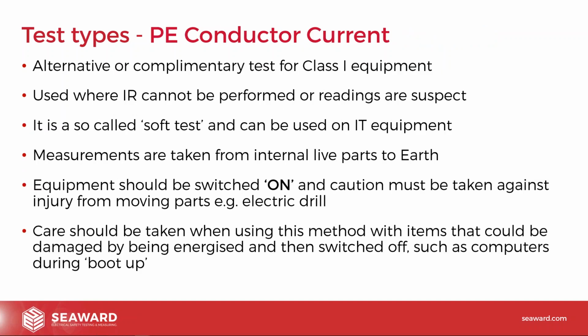So protective earth conductor current testing. So what are we doing? Well, basically we're measuring the quality of the insulation by connecting mains to the equipment, and then we're measuring how much of that current actually leaks back to earth, actually travels back down the protective conductor. Now, generally, the way we do this is by measuring the difference between the line current and the neutral current. And in theory, if there's no leakage, obviously the line current and the neutral current should be the same. If there's leakage through the insulation, then we will see a difference between those currents, and that will generally be measured by the PAT tester, and it will give you a measurement of the leakage current.